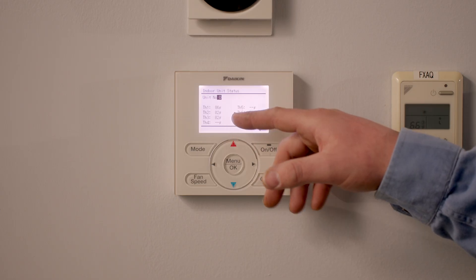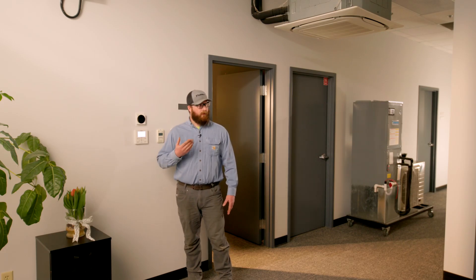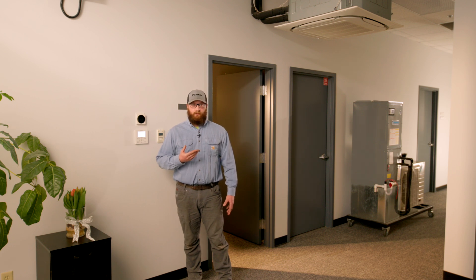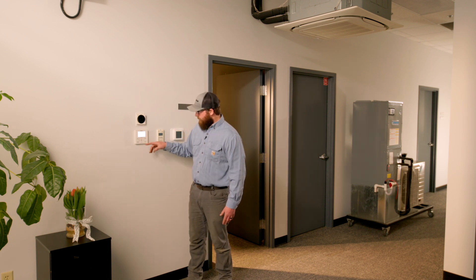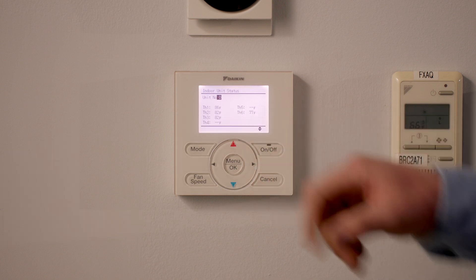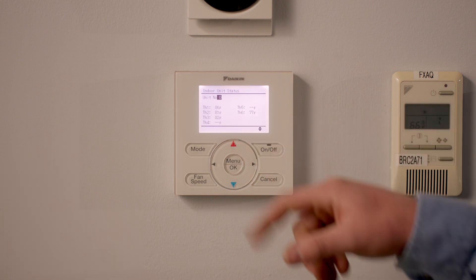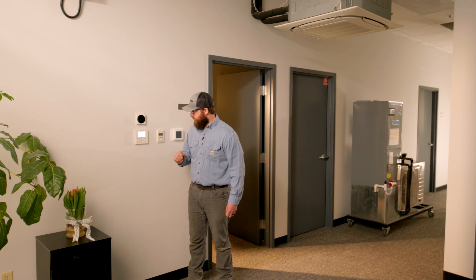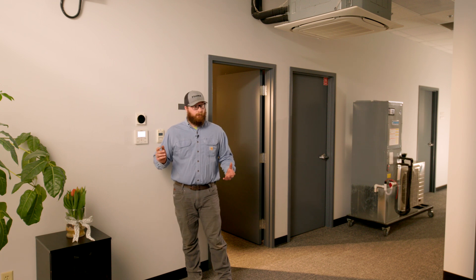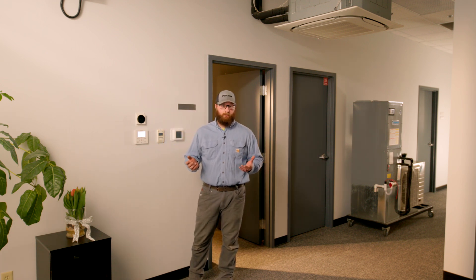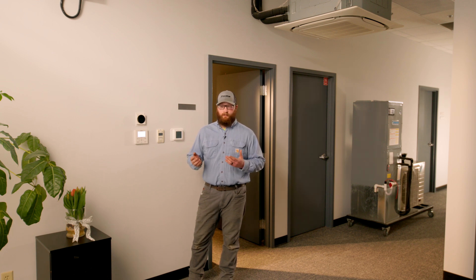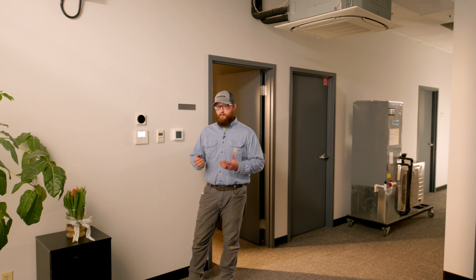A good thing about this is that you can actually see if your indoor unit's not cooling. If you come up to this menu and you had skewed numbers like 40 degrees on TH2 and 50 degrees on TH3 and we're not moving any air, that means we have what we would call liquid bleed-by through the valve, and that's not good. That's how we destroy compressors on VRV equipment.